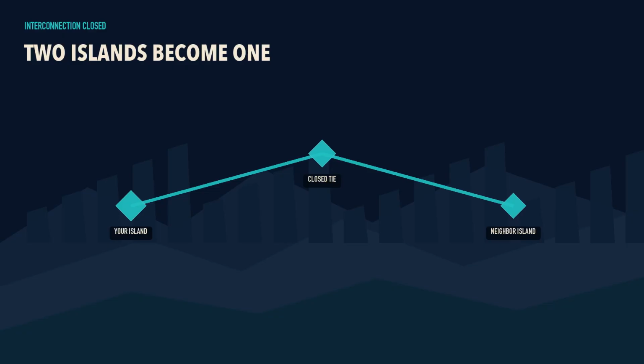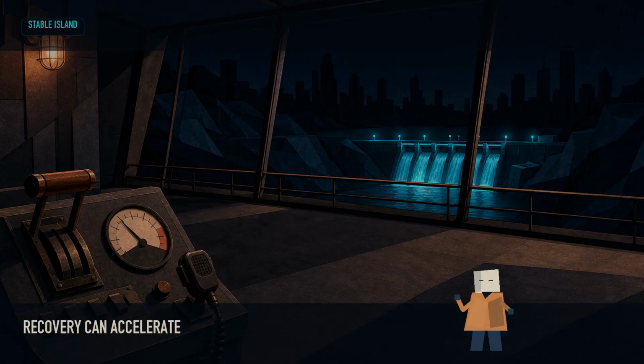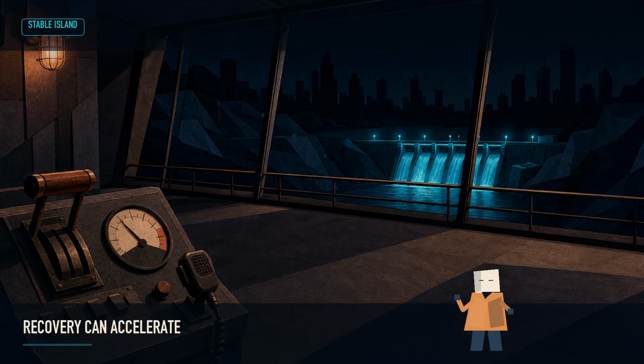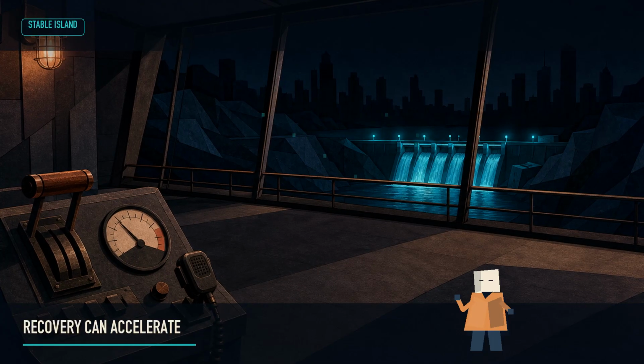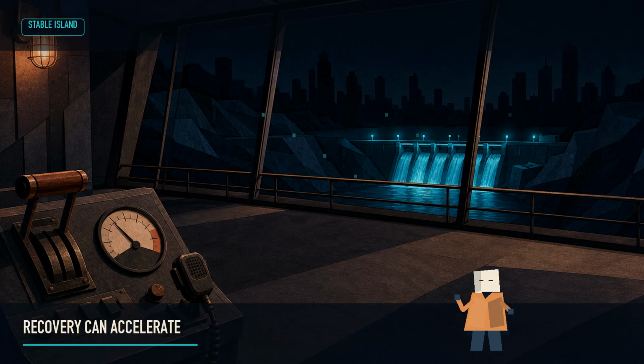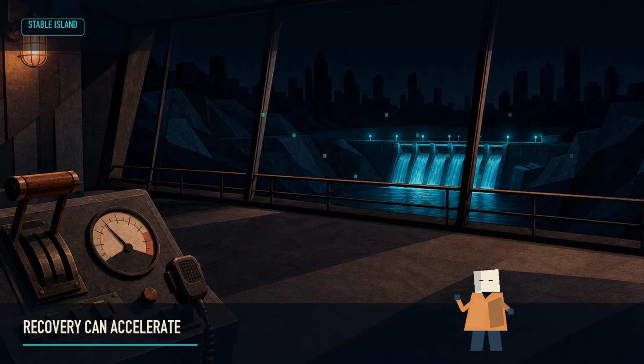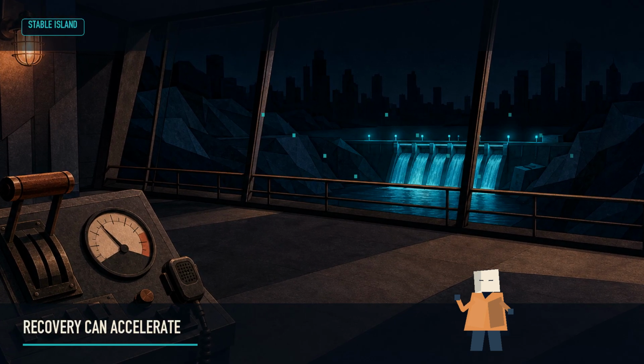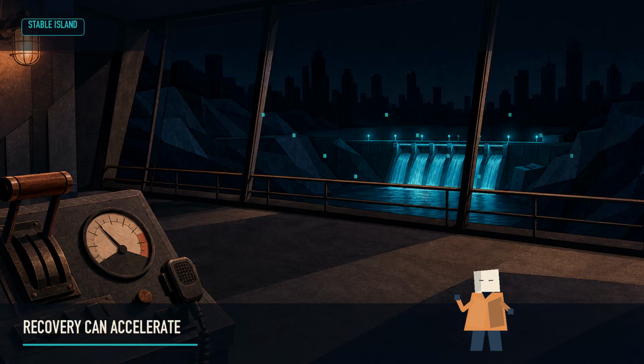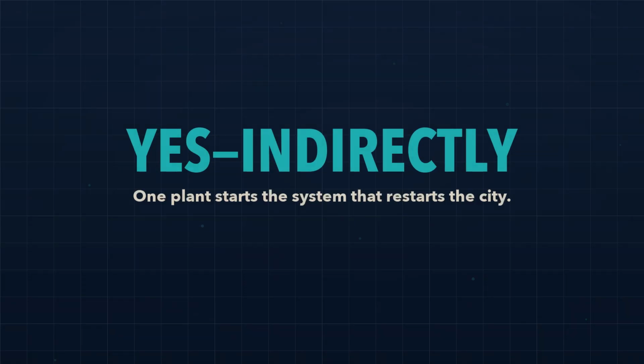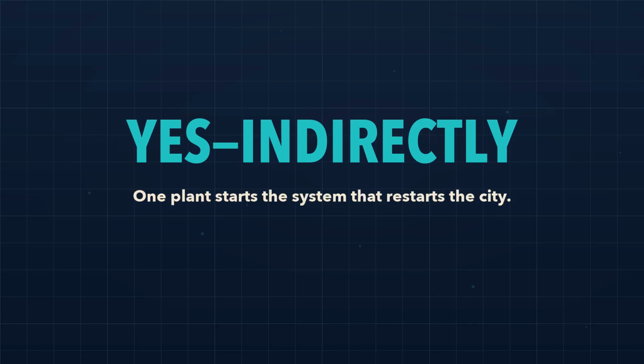More routes and more reserve are suddenly available. The city is not fully restored. Many homes are dark, damaged equipment remains isolated, and every new block still needs checking. But essential services are stable, more generation is online, and the recovery can now accelerate. So, can one power plant restart a dead city? Not by powering the city directly. It can create the first stable electricity that wakes other generators, control systems, transmission paths, and carefully selected loads.